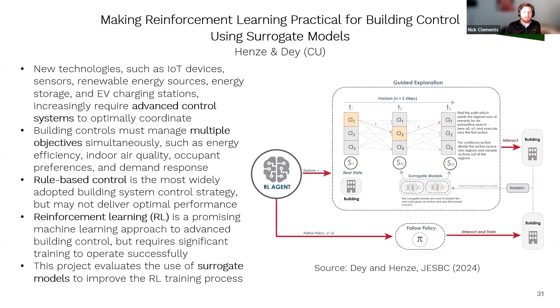They applied this reinforcement learning algorithm to a case study: a small office building with multiple zones in Chicago. It's got a constant air volume air handling unit, gas heating, DX cooling, and industry standard control sequences, plus a PV system and battery to store and generate energy. The algorithm tries to reduce energy consumption cost, reduce thermal discomfort, and avoid demand response costs all at the same time—that's where the multiple objective aspect comes in.